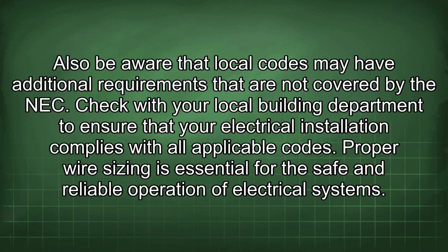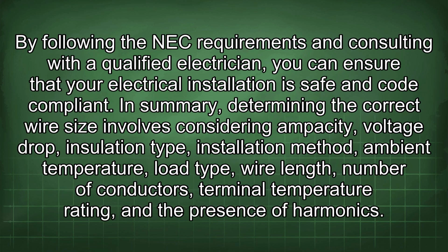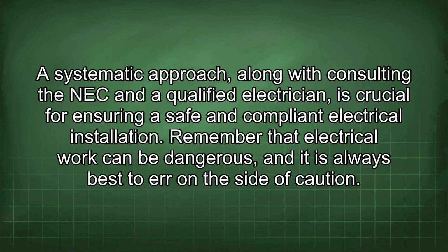Proper wire sizing is essential for the safe and reliable operation of electrical systems. By following the NEC requirements and consulting with a qualified electrician, you can ensure that your electrical installation is safe and code compliant. In summary, determining the correct wire size involves considering ampacity, voltage drop, insulation type, installation method, ambient temperature, load type, wire length, number of conductors, terminal temperature rating, and the presence of harmonics. A systematic approach, along with consulting the NEC and a qualified electrician, is crucial for ensuring a safe and compliant electrical installation.